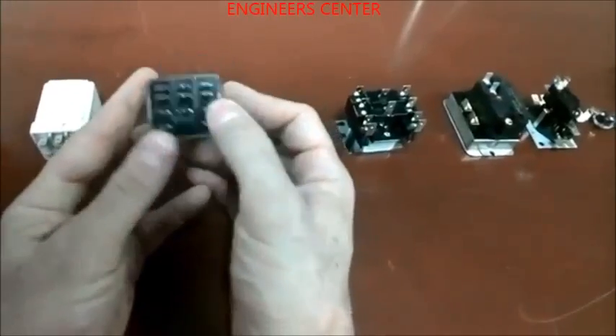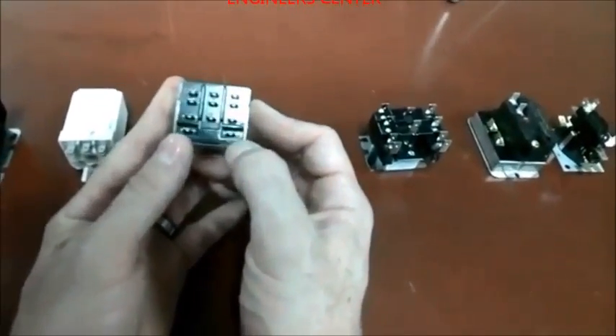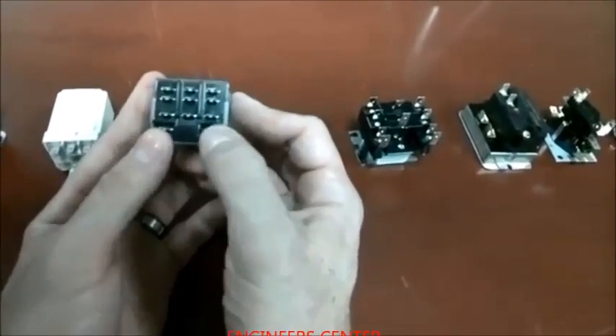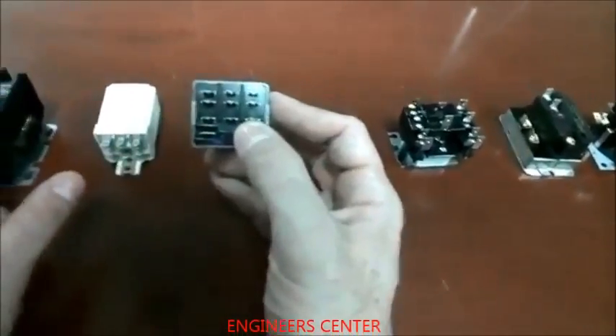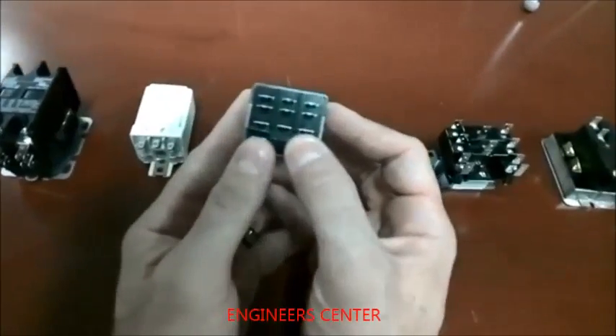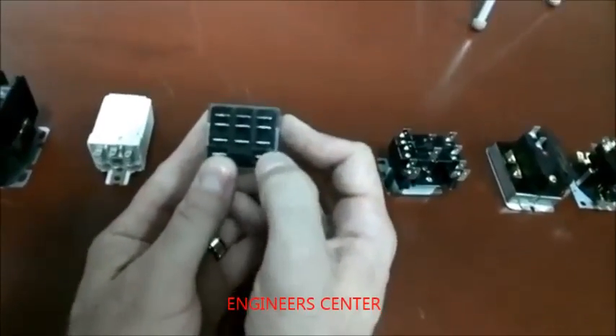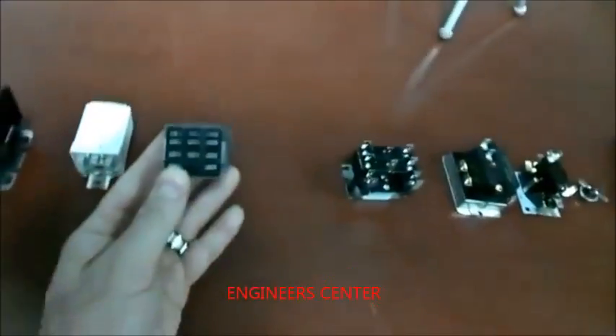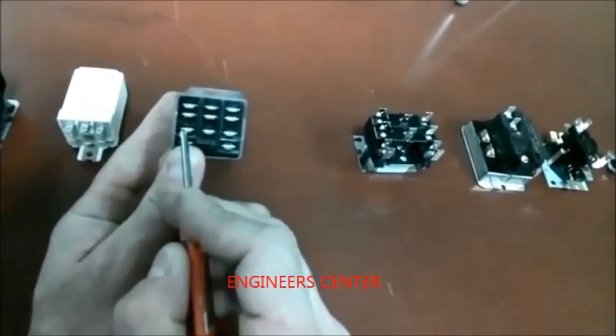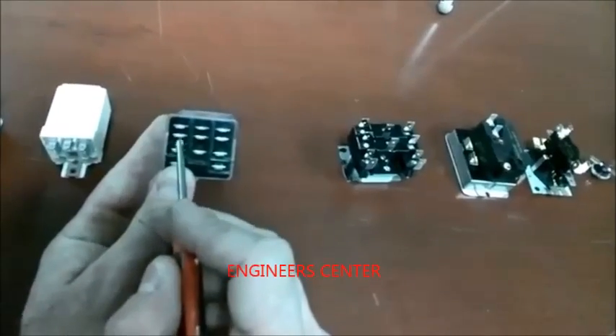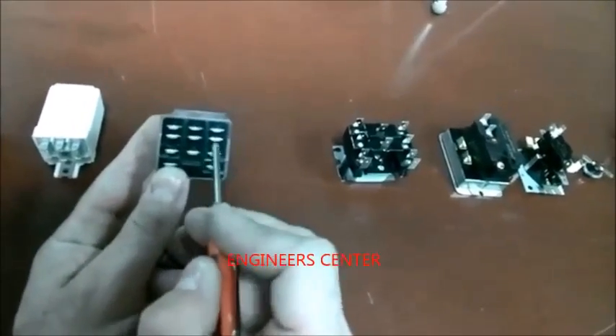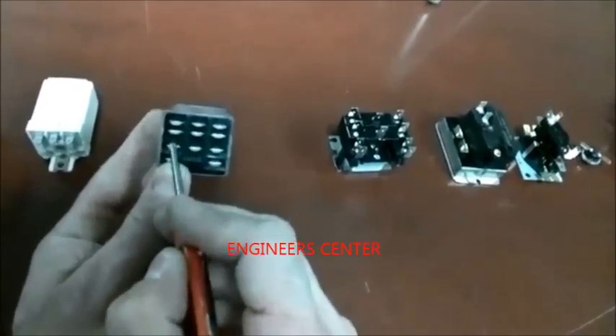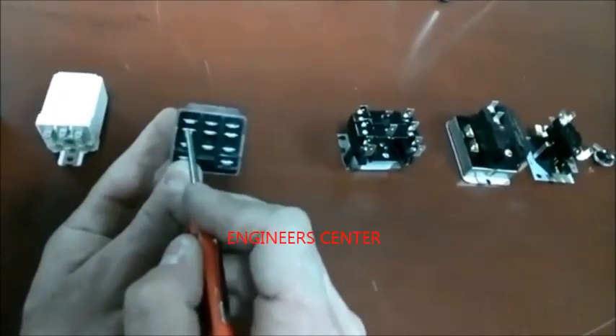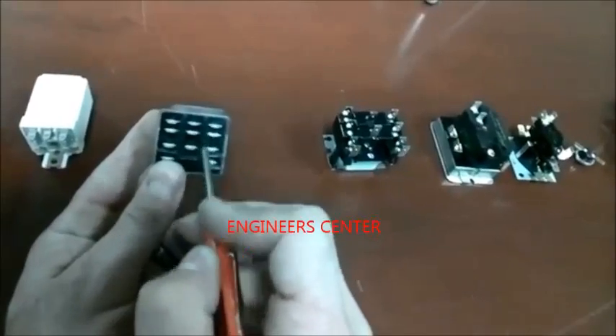So these here, just simply the very bottom two, A and B down here, are your 24 volt coil. And just like this relay, this does the same thing, except this is just 3 different relays. You could put power here, here, here, or here, and this is normally closed to there, and to there. So these are closed, these are closed, these are closed. But if you give it power, this will now de-energize here and switch up to here. Same for all 3, so you have 3 different circuits. So you just have to understand what a part is and what it does in order to troubleshoot.